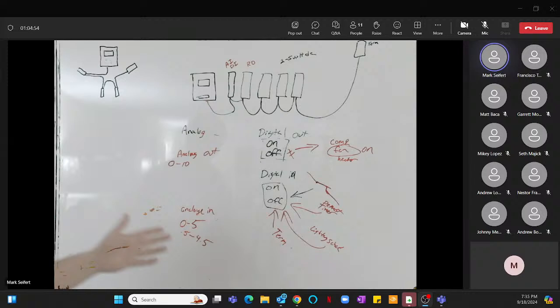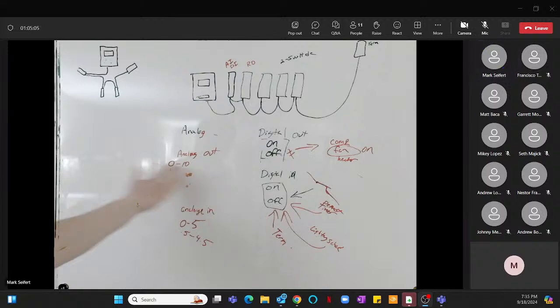So analog in is analog. It's like your analog gauges. It's anywhere between 0 to 10 here and 0 to 5 there on the inputs. We don't have much that's more than 5 volts on inputs, except for things like light level sensors and humidity sensors. Those are going to be higher inputs.